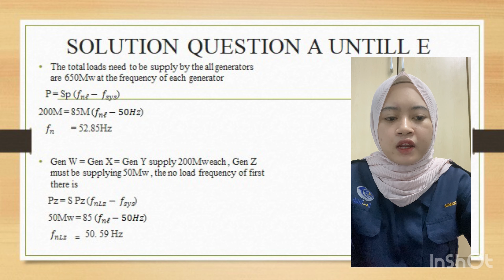If generator W, generator X and generator Y supply 200 megawatt each, generator Z must be supplying 50 megawatt. The no load frequency of generator Z is F NL Z equal to 50.59 Hz.